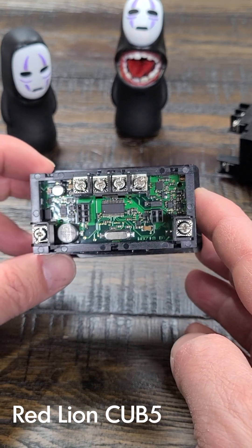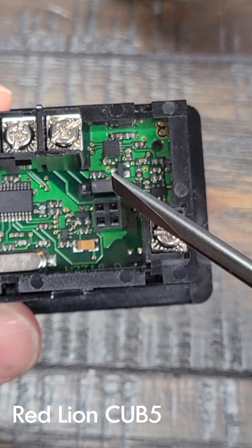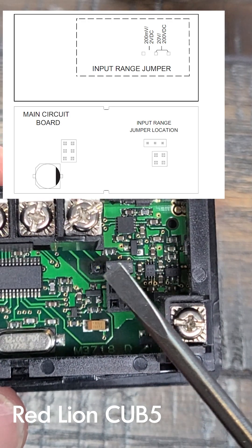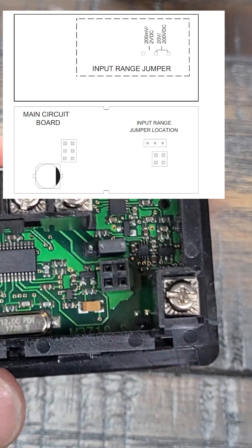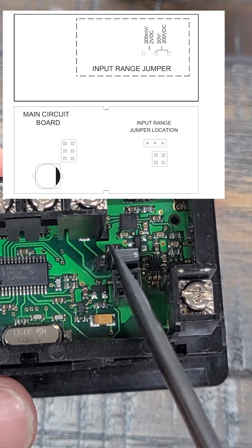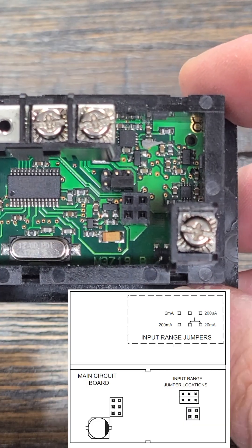On the Cub5 V-Type, once you get the back cover off, you'll see the jumper pin right here. Out of the box, it's set for up to 20 volts or up to 200 volts, depending on how you set the menu settings. So if you have a lower voltage input, you can take this, pull it out, and move it over to these two points. You can connect a 200 millivolt or 2 volt input.